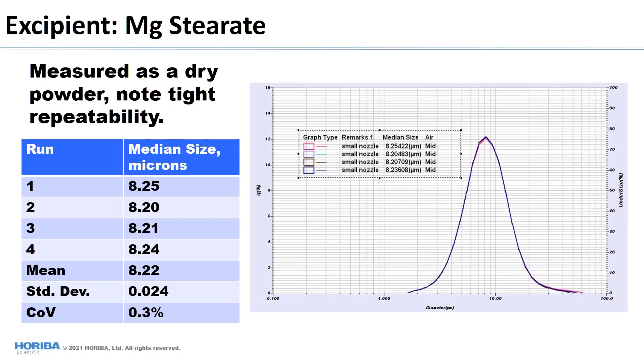Moving to practical examples: magnesium stearate run four repeats as a dry powder shows a median size of about 8.2 microns, a standard deviation of 0.024 microns, and a coefficient of variation of 0.3%. The size distribution graphs overlay quite nicely. This rests on two things: in the dry powder measurement, we run the sample and then take a fresh batch for the second run — so not only is the analyzer repeatable, but our splitting and sampling consistency is repeatable as well.